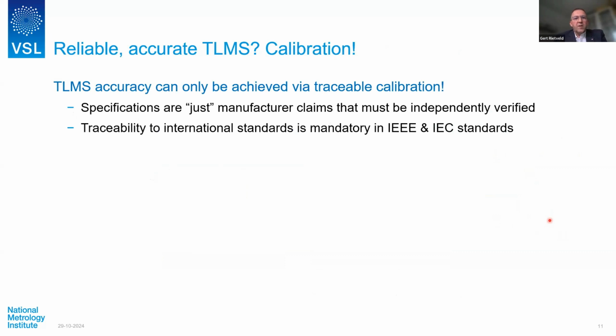So the power transformer manufacturers have this equipment, but that still does not automatically mean that the equipment is indeed meeting the requirements set by the IEEE or by the utilities. So they want an independent verification of the accuracy of this industrial measurement system. And that's where we metrologists come in, where calibration comes in. This traceability to international standards is mandatory in the IEEE and IEC standards. And the rationale behind this requirement is what I showed in the very beginning. If you want to do a reliable test, and this test has an enormous impact financially and also environmentally, you should really be sure that your equipment is traceable to national standards. So we should calibrate it.